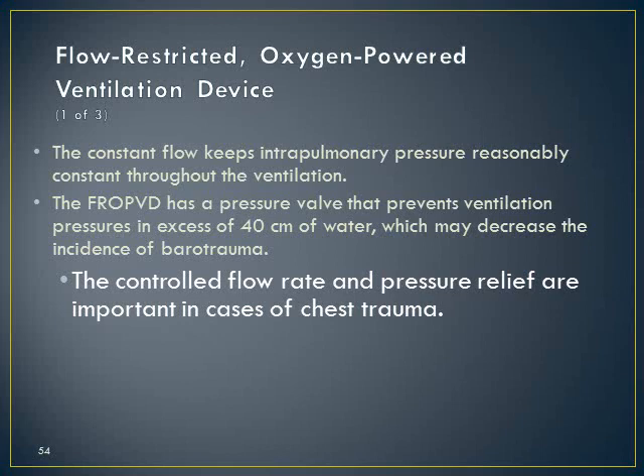We also have a pop-off valve or pressure valve that will release pressures of greater than 40 centimeters of water, which will decrease the incidence of barotrauma. But realize if you have somebody that's got COPD or already has a weakened spot, we can still potentially cause a pneumothorax by using these devices. So we want to be careful when we use flow-restricted oxygen-powered ventilation devices.